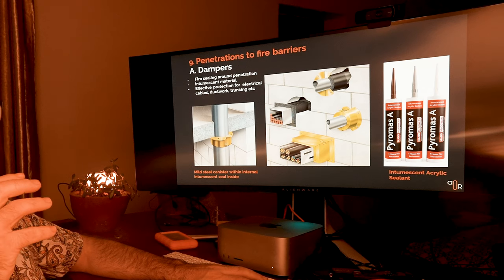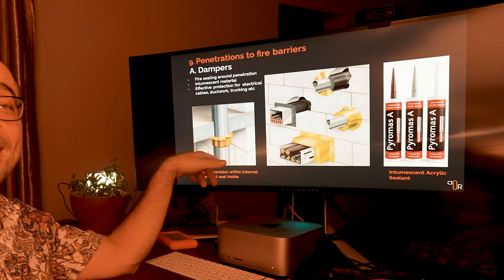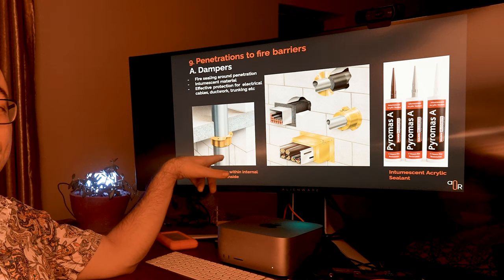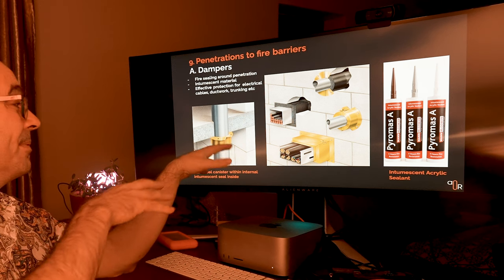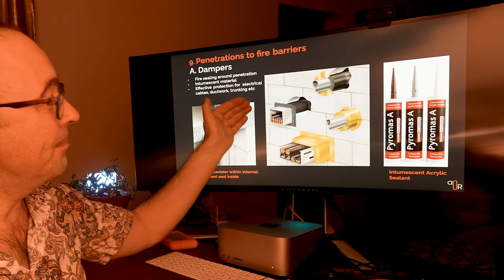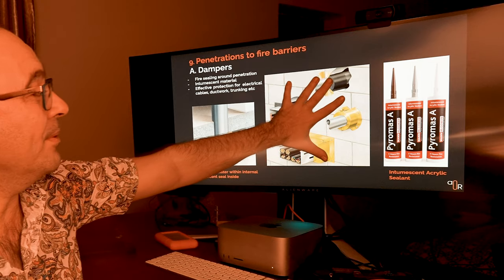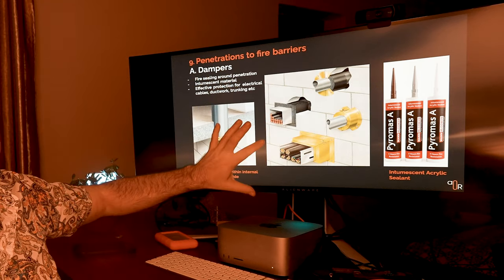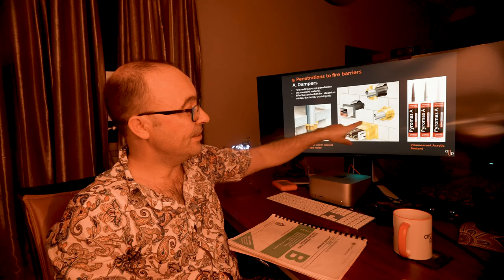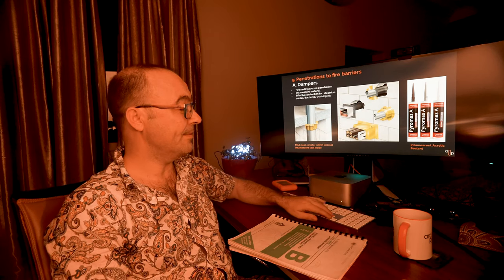Penetrations in these fire-rated walls also need to be protected. If you're putting pipes and stuff in these walls, they've got to have dampers — an intumescent strip around the seal of the penetration. That's a fire wall protected area — there might be an office on one side and a shop on the other, so you've got to protect that so the fire doesn't go through.